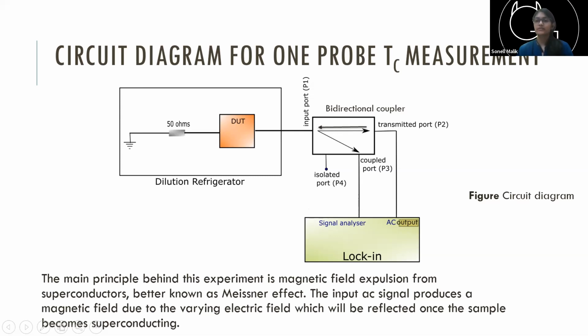Now, a lock-in amplifier, especially for first and second year students who don't know, is something where you can select a very particular frequency that you want to measure, because the signal will be very small. The reflected signal will be very small, because in a bidirectional coupler, most of the signal will go here into port 2, and with almost a 10 dB power reduction, some of it will come to the signal analyzer. If we know the exact frequency, which we do because we're giving in the AC input to our device, then we can check for that frequency and see how much of that frequency signal is coming in, the amplitude of the signal.